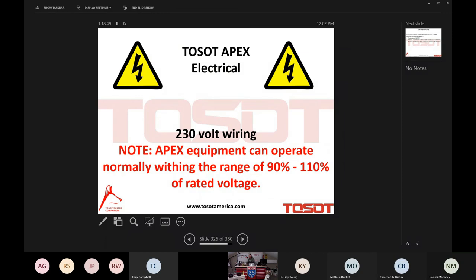So what does that mean, right? It means you're good for 10% plus or minus. Right? I'll be honest with you. You're a little bit better than that, but we want to be conservative, right? But that's what that's saying. As long as we are within 10% plus or minus of the rated voltage requirement, 208, 230, we're good to go, right?